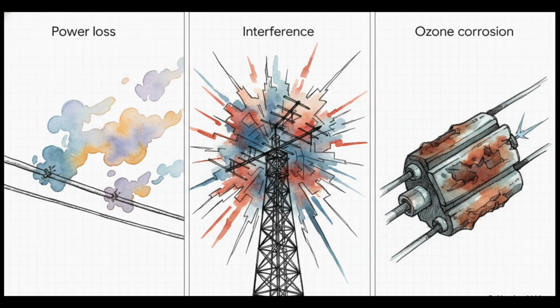First off, there is a direct, real power loss. The grid is literally bleeding usable energy into the sky. Operators call this corona loss. Second, all that ionization creates electromagnetic interference. It can completely disrupt local radio and television signals. And finally, remember that metallic smell? That's the generation of ozone gas. Now, ozone is great high up in the atmosphere for sure, but down at the conductor level, it causes terrible accelerated corrosion on the system hardware. So yeah, it's a costly, damaging electrical leak.